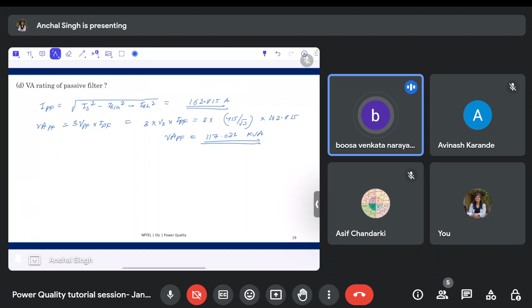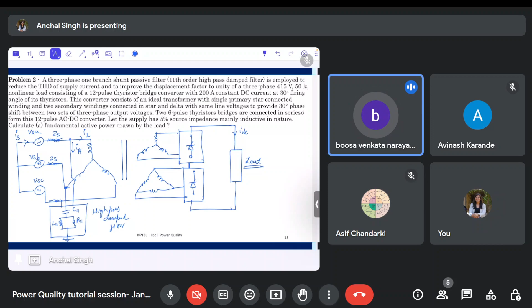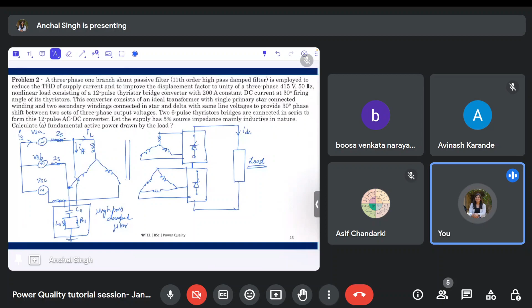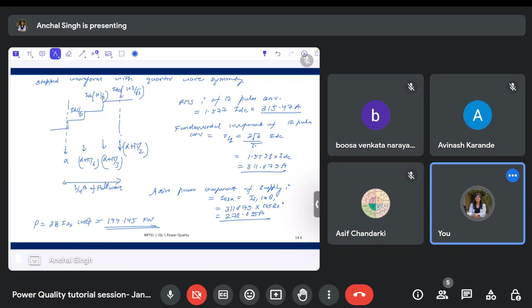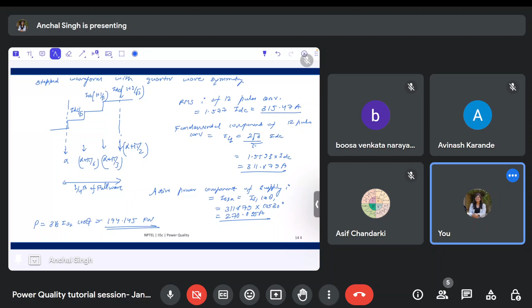Because the rest, 11th and above harmonics, are taken care of by this high pass damped filter. But we have to subtract IS square minus I11 square, madam. Yes, so the current we obtained here, you can directly call it I cos theta. The only active part of the current will be supplied, which is the active power component of the supply current, IS1 cos theta 1. So only this part will be supplied by the current after applying the passive filter. But these calculations are valid only for the full load condition. When the system operating point changes, these values will change. Since you are designing for the full load condition, right now perfect compensation will be present, but later the compensation will not be absolute.